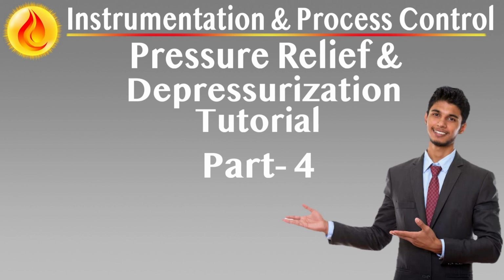For 50% of set pressure, use balanced bellows spring-loaded valves. 70% of set pressure, use pilot-operated valves, provided cleanliness and other service requirements are met.